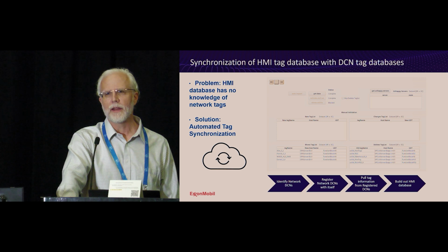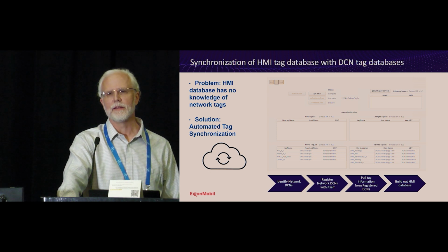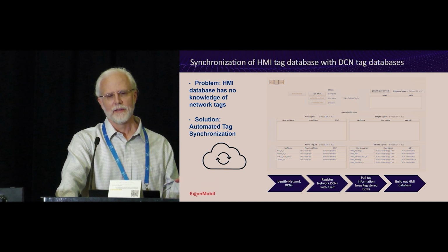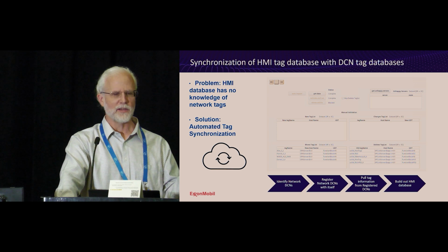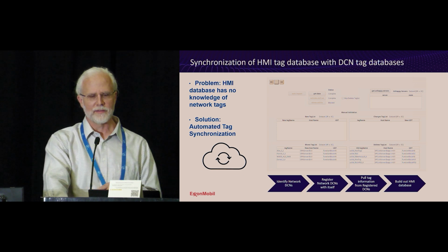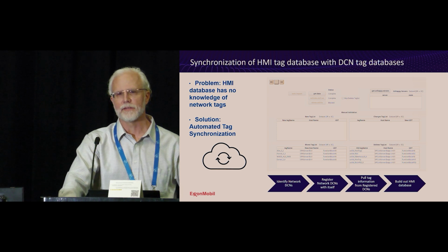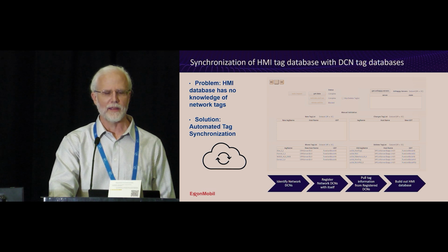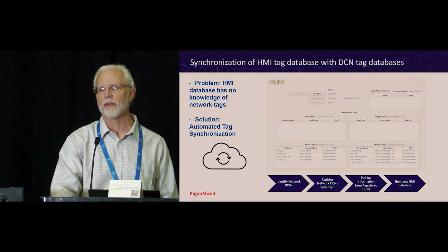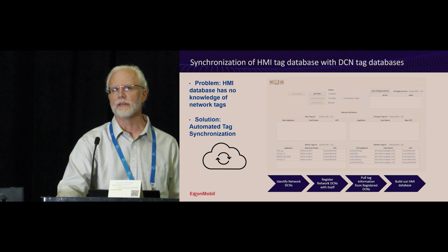If you don't have this automatic synchronization, it's very difficult to keep things up to date. If anytime somebody changes a range on an instrument and you have to change it in the control system and you have to change it in the HMI, it's just a matter of time before these things get out of sync. So this idea that we avoid rework and that we have this built into the process was another part that was really paramount to the overall design.